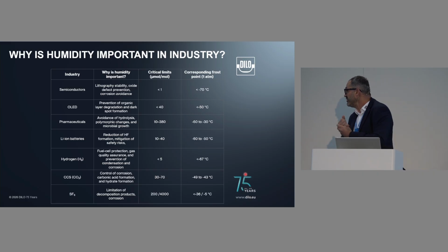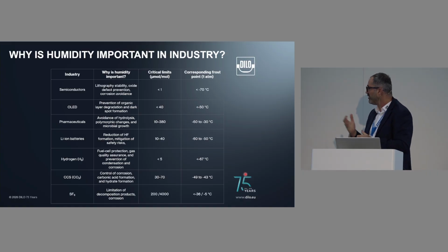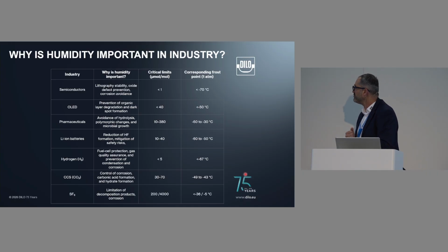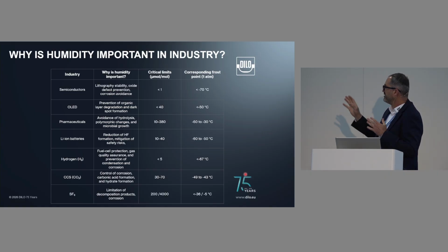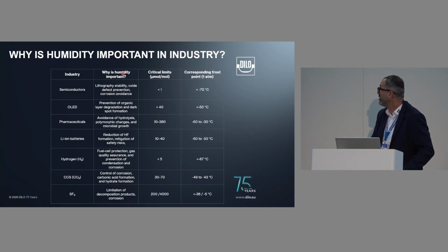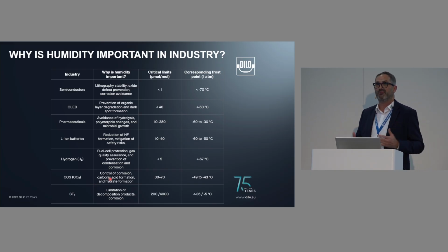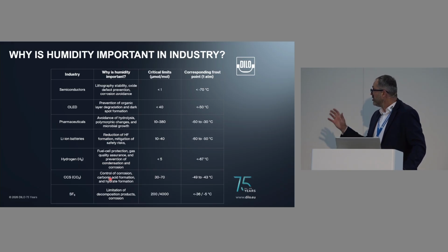Also here, why it is important, especially for industry purposes. We have also heard a lot of this in the previous two presentations. I don't want to go into detail, but this table illustrates that there are a lot of industries that rely on good humidity measurement, but for different reasons. For example, for product quality, for chemical stability, for safety risk, for corrosion, or in general for the gas quality or the lifetime of the components. Those are good reasons for accurate humidity measurement, especially when it comes to very low humidity values and humidity in different carrier gases.